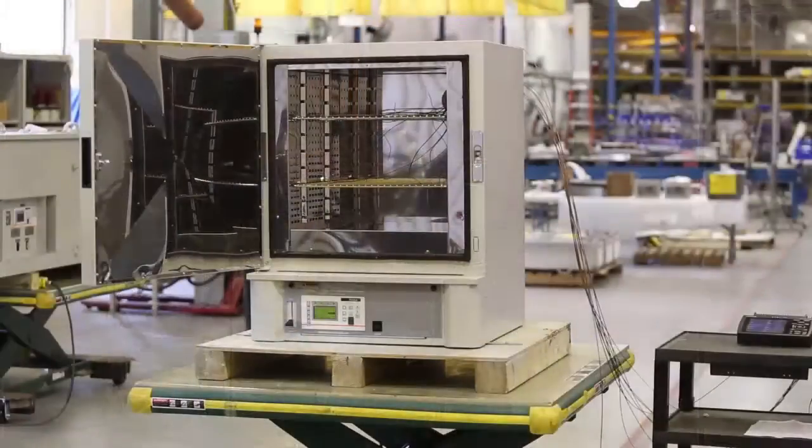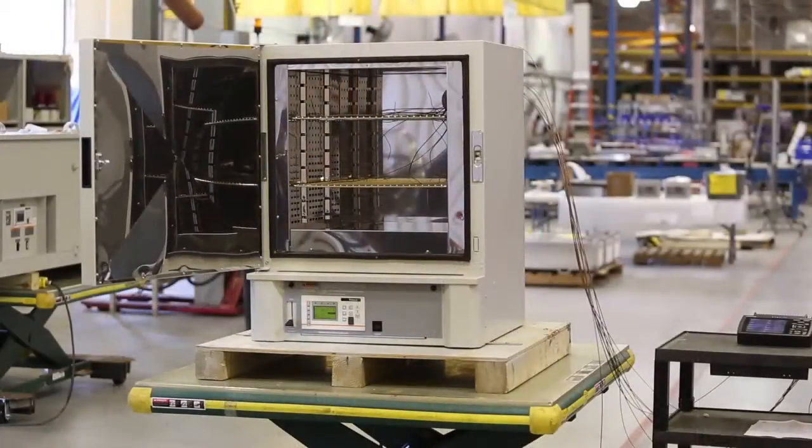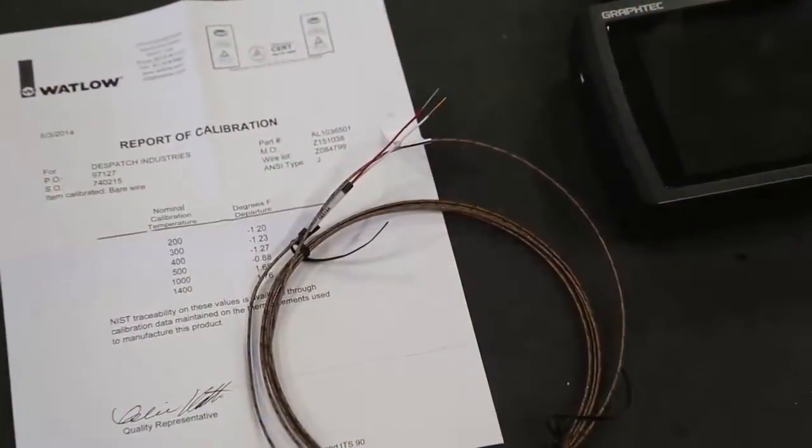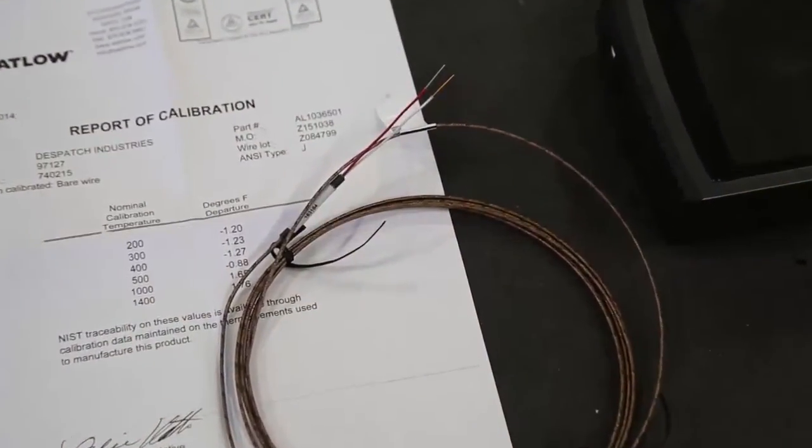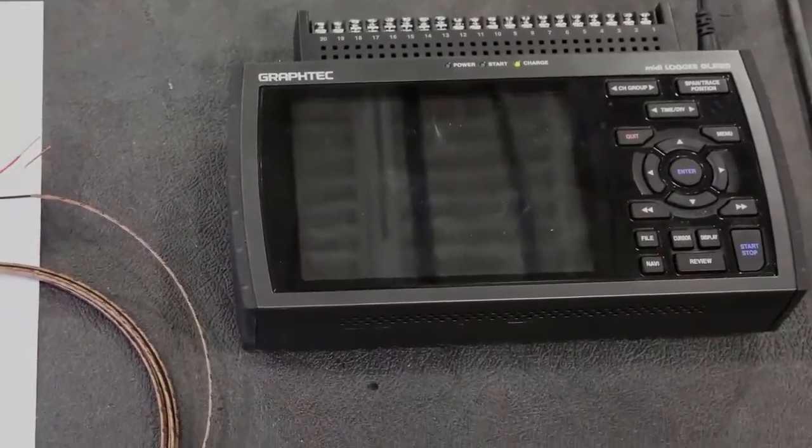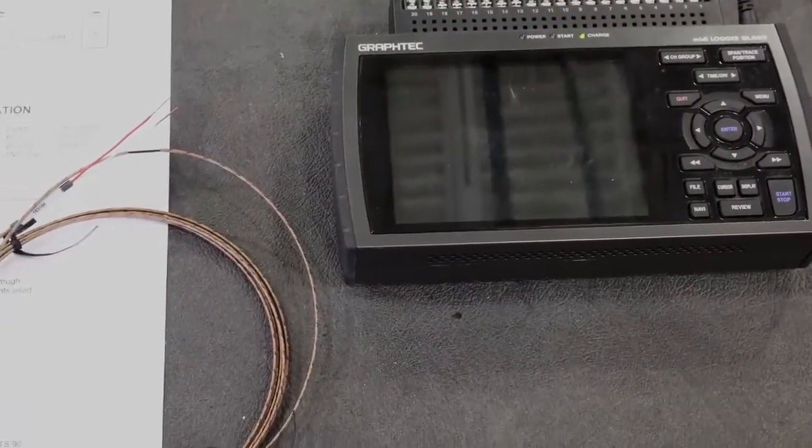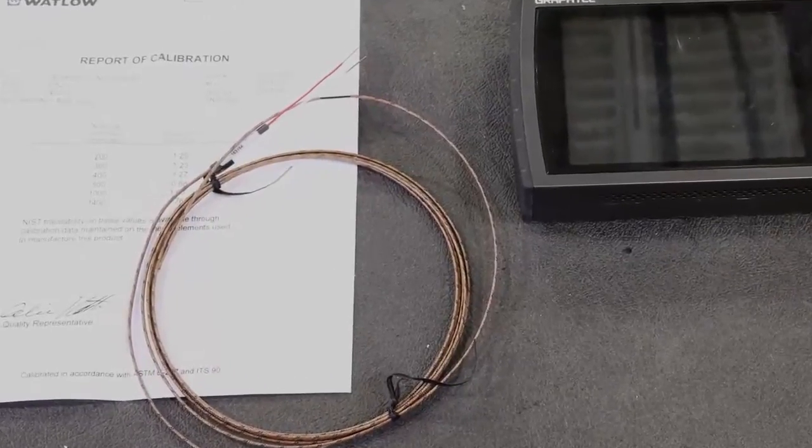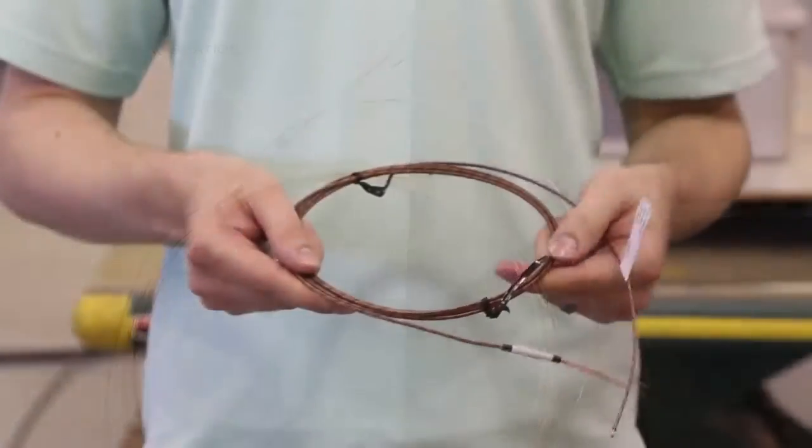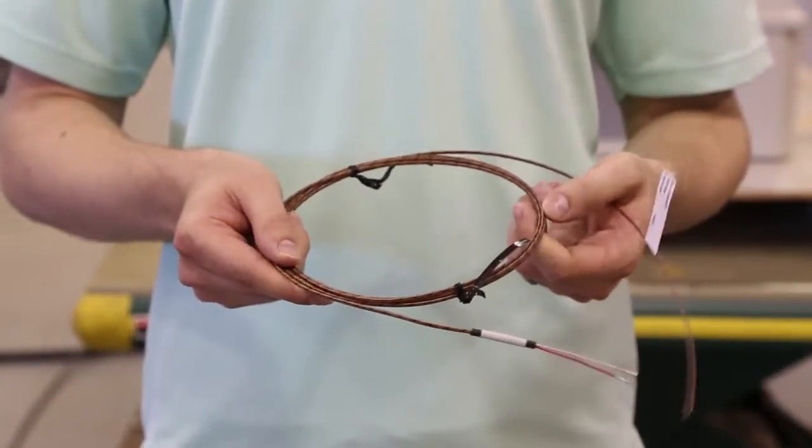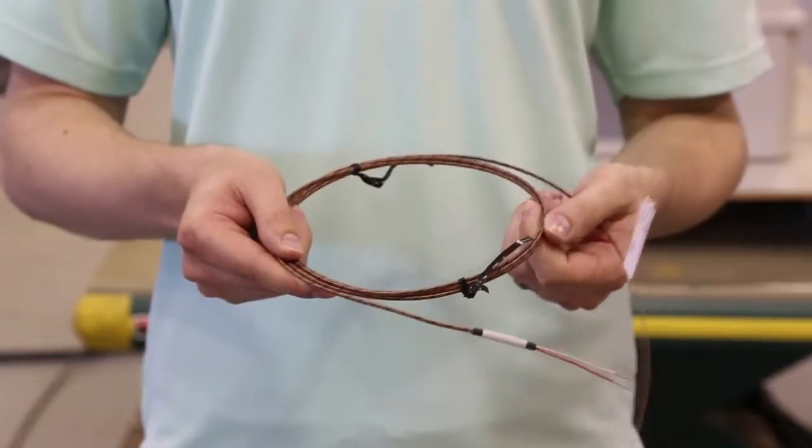In this demonstration, we will be conducting the test with no load. To complete this test, you will need nine thermocouples and a nine-point temperature data logger. Be sure to use certified thermocouples that have not been degraded with repeated use. For the best accuracy, we will use brand new thermocouples.